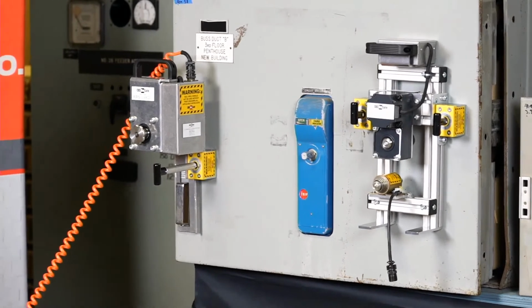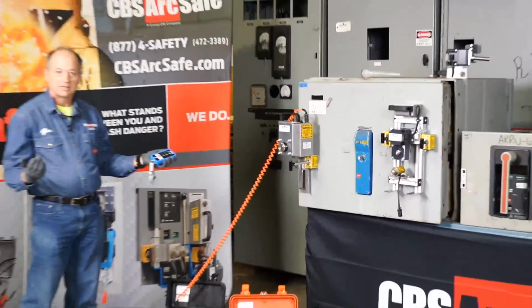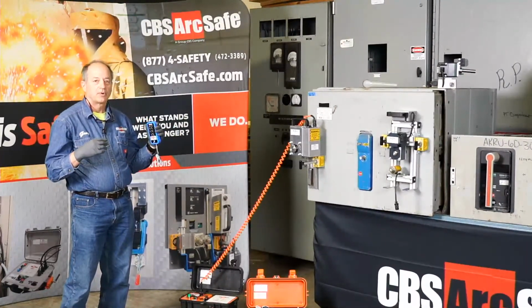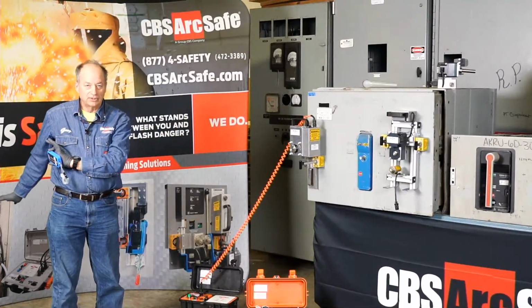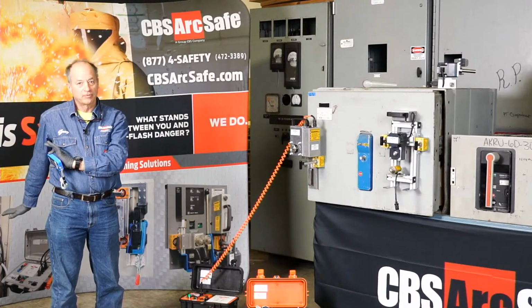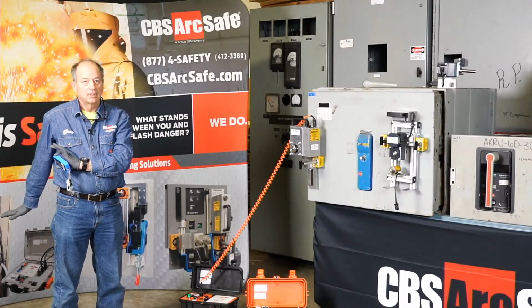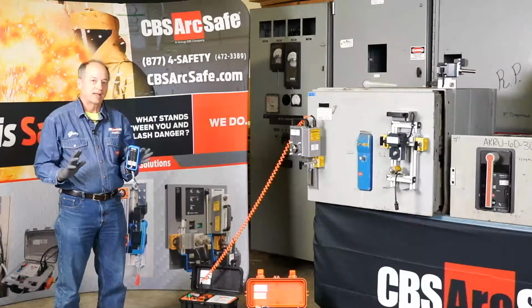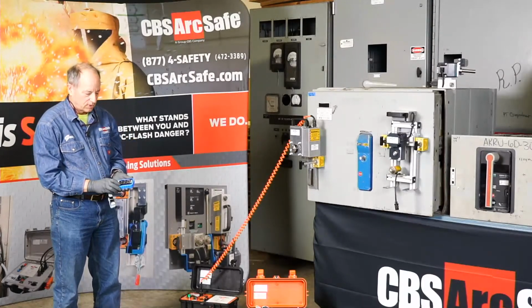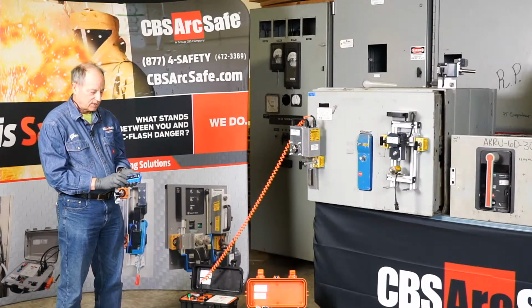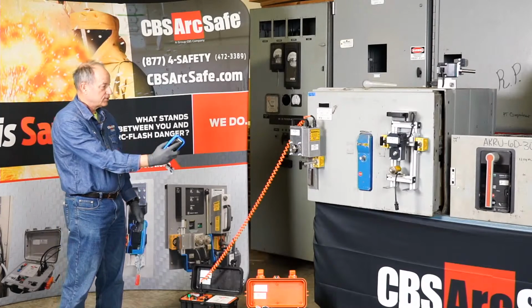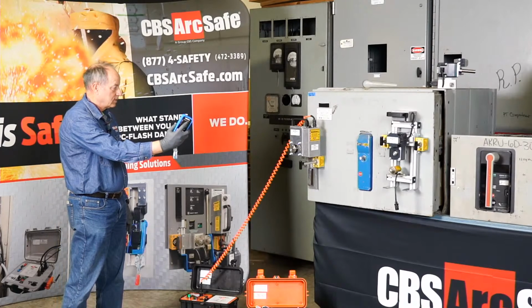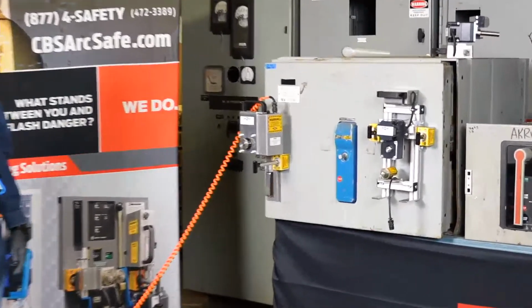At this point, if you do your lockout tagout, you would then work to do whatever work you're needing to do downstream or remove the breaker from the cubicle. And then when you put your new breaker back in the cubicle, you'd make sure you've got all your lockout tagout done. And then you'd hit your install button. And we're going to rack the breaker back in now.